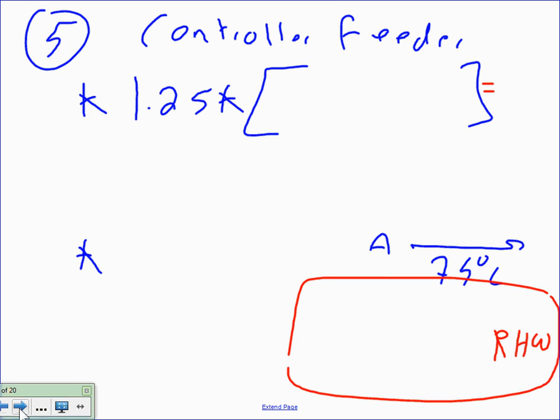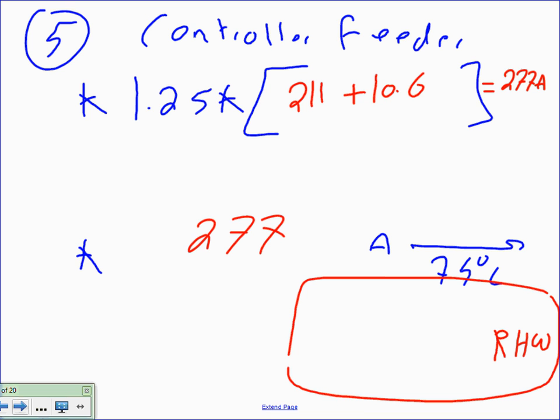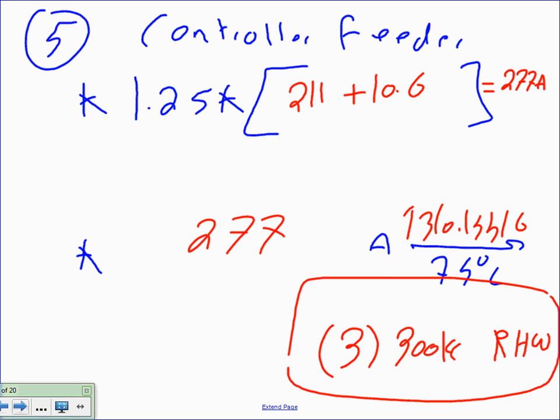Okay, controller feeder. What you guys do is you take the full load amp of the pump, add to it the full load amp of the jockey pump. That will give you 277 amps. And if you take the 277 amps to table 310.15(B)(16), you are going to end up with 3 conductors. Each one of them is how many? 300 kcm, RHW.